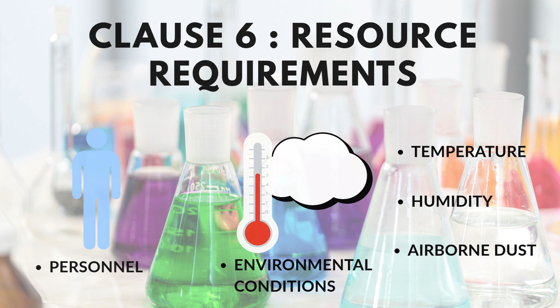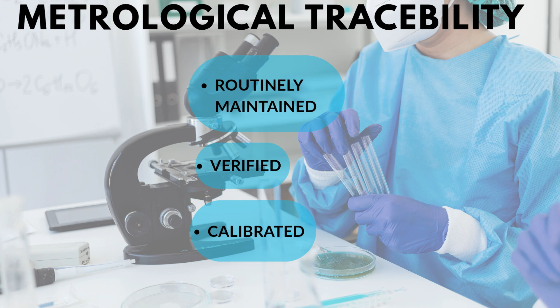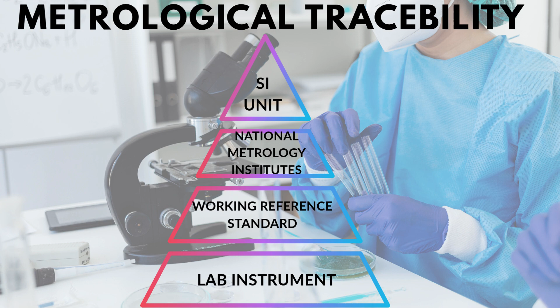Second, the standard regulates the facilities and environmental conditions. In analytical chemistry, ambient temperature, humidity, or even airborne dust can alter chemical reactions and instrument performance. An accredited lab must continuously monitor and record these conditions. Third, we have equipment and metrological traceability. All analytical instruments must be routinely maintained, verified, and calibrated. But calibration isn't just about resetting a machine to zero. It requires metrological traceability. This means the calibration of your lab instrument must be linked back to an unbroken chain of comparisons reaching all the way up to the international standard, such as SI units. This ensures the measurement taken in our lab will match a measurement taken anywhere else in the world.